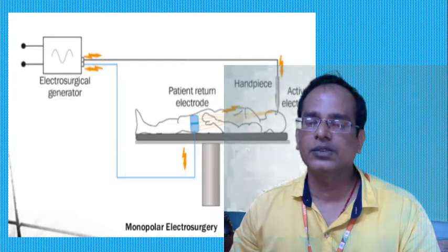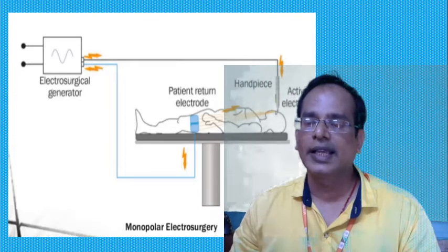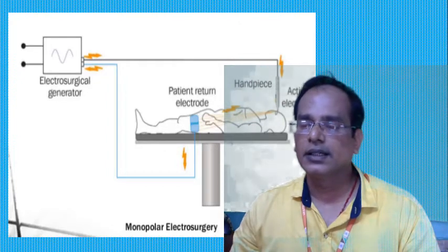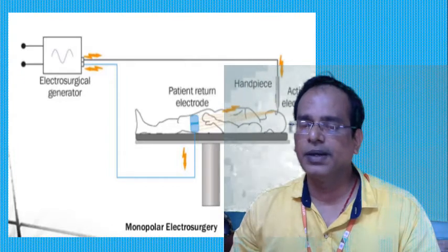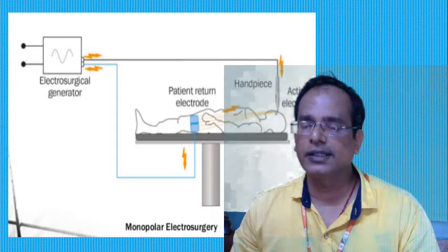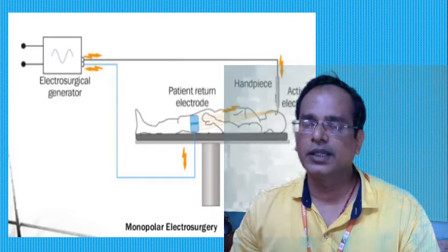So they are using Joule's first law for electrosurgical instruments, based on the principle of converting electrical energy into heat. The relation between the amount of heat and the electric current depends upon Ohm's law, that is R, the resistance, and the duration of time. So the heat is calculated as current squared into resistance into time.